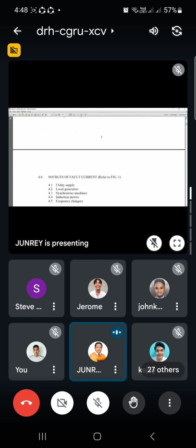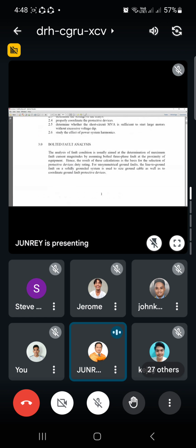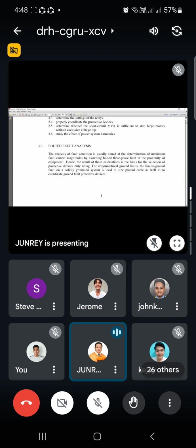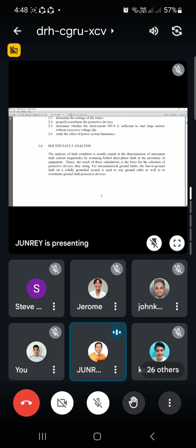That is why when we do the reactance diagram, we consider, for example, the generator: is it bolted? Is it solidly grounded? Then you consider that, because it has an effect on your fault current.